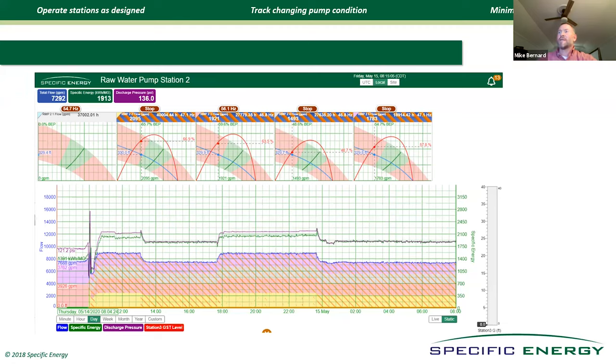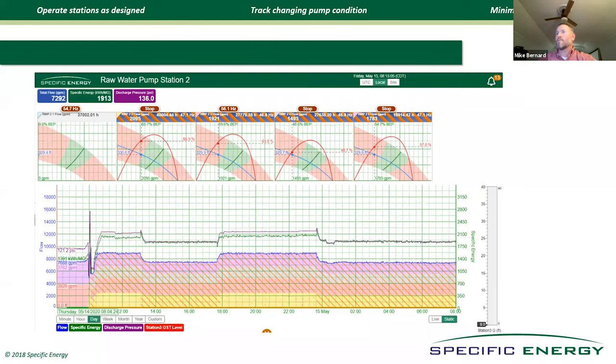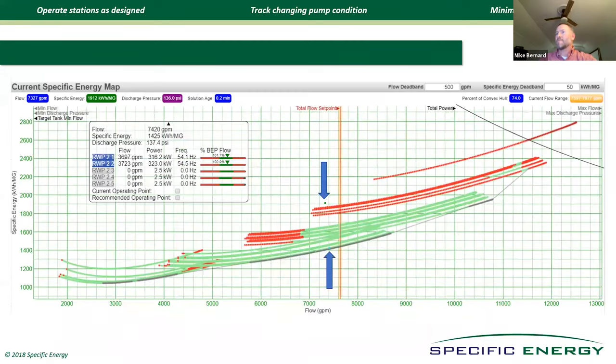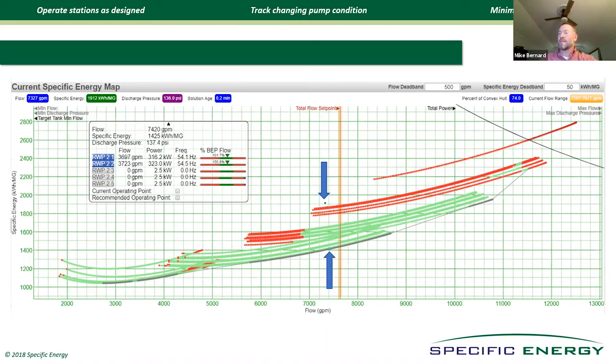He said, well, we put the system in about five years ago and then ran it in DPO mode for a while, but then the plant manager thought he could do a better job. And so they kind of just haven't paid attention to it. I said, really, do you mind if I try to bring them back into the fold? So I took this screenshot and I sent it to the email address that I had on file and said, hey, I just want to introduce myself. I'm Mike Bernard. I'm now with Specific Energy. I thought I'd bring something of value to the introduction. And so I thought you'd like to know that if you just turned one of your pumps off and sped the other three pumps up, you'd have much happier pumps and you'd save about 25 to 30% energy.